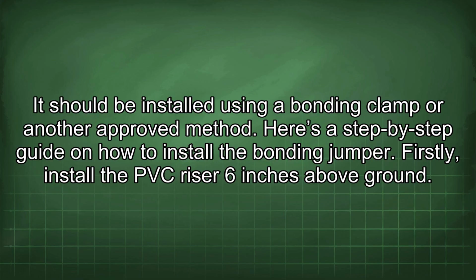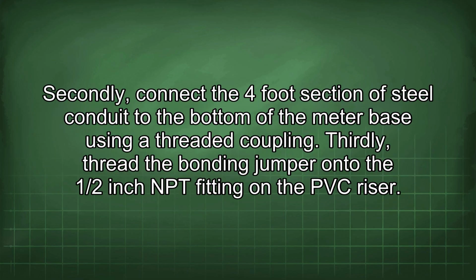Here's a step-by-step guide on how to install the bonding jumper. Firstly, install the PVC riser 6 inches above ground. Secondly, connect the 4-foot section of steel conduit to the bottom of the meter base using a threaded coupling. Thirdly, thread the bonding jumper onto the 1/2" NPT fitting on the PVC riser.